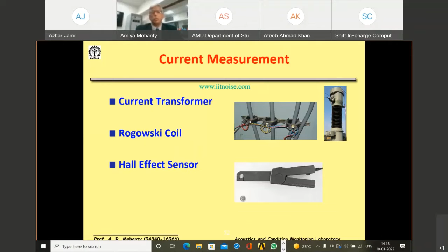The idea is, first I need to measure the current. I can use current transformers, Hall effect sensors, or a Rogowski coil - these are all measurement devices. Once I have the current, I use cheap data acquisition units, less than 15,000 rupees, USB plug and play, feeding into an FFT analyzer or a microcomputer. This is what we started with in 1998. So all I require is a Hall effect sensor, data acquisition unit, and an FFT analyzer.